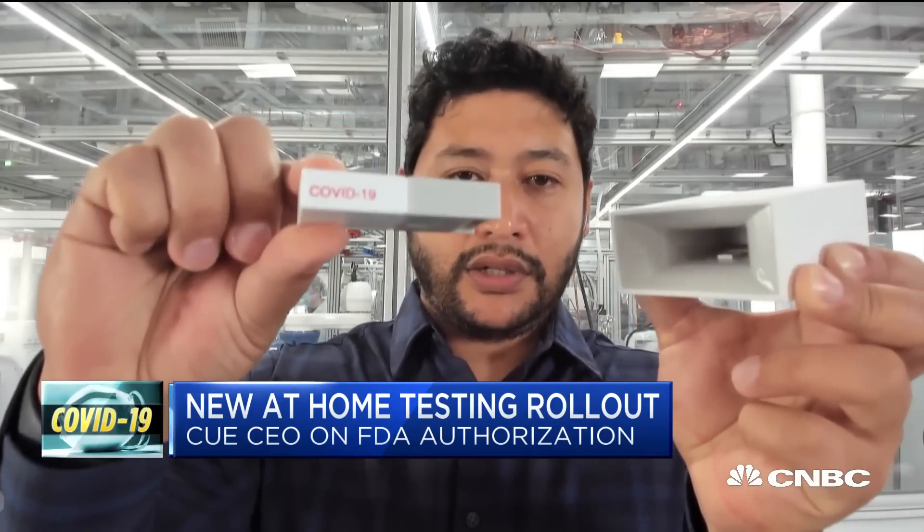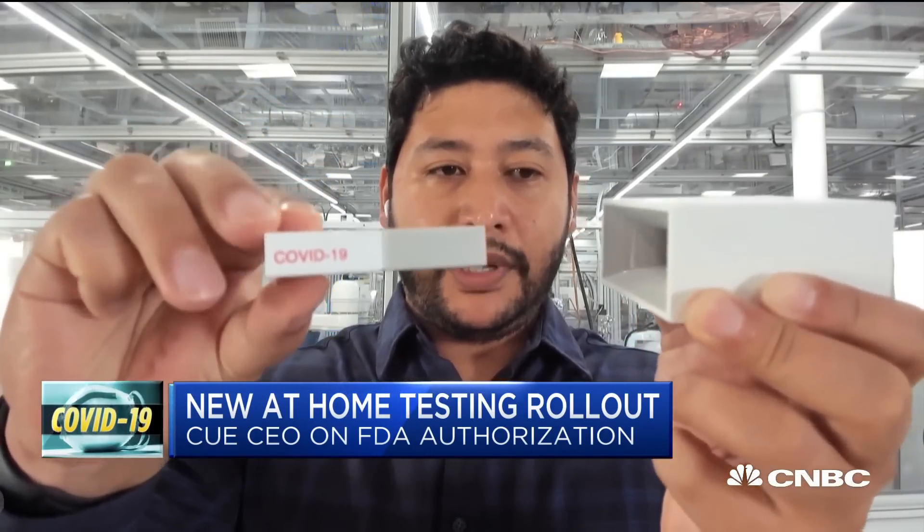It's a point-of-care diagnostic that works very quickly — you can get an answer in 25 minutes. So this is the Cue reader, and this is the COVID-19 test cartridge. What you do to operate it is insert the cartridge into the reader, then use the provided nasal swab to take a sample, insert the swab into the cartridge, and the test starts automatically. Results are delivered in about 25 minutes to your mobile device.